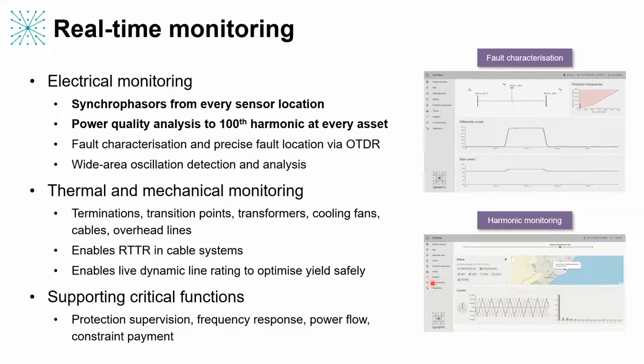Yeah, so that's a very good question. Obviously we can respond to the fault when it has occurred, and we can do that more granularly than a traditional protection system. That's nice, but the real question is how much in advance can we predict that fault's going to happen so that operators can intervene before it becomes a problem. This is something that we think about a lot at Synaptec, both for offshore and underground cable applications. If you can get data on, for example, the cable terminator or junction box temperatures and the power quality at all the infeeds correlated with the current, then you can start to get a full picture of the reasons for degradation and the sources that are causing, for example, low power quality.